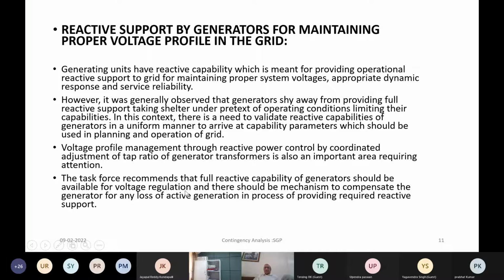So here it is prioritizing reactive power support when it is critically needed for grid stability, against the loss of MW to enable that. We saw in the capability curve yesterday that the reactive power capability somewhat gets reduced as you fully load active power. If you remember the shape of the curve in the overexcited region, the full reactive capability can be achieved at 0 MW. That is the maximum. But as you pick up active power, the reactive power reduces to some extent. This is basically to control the overheating of the armature as well as the core of the generator. This restriction is required to be maintained as per the capability curve.